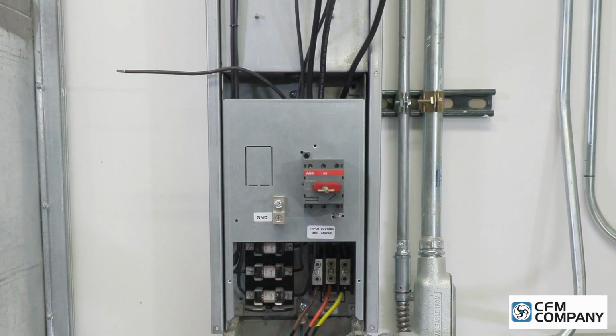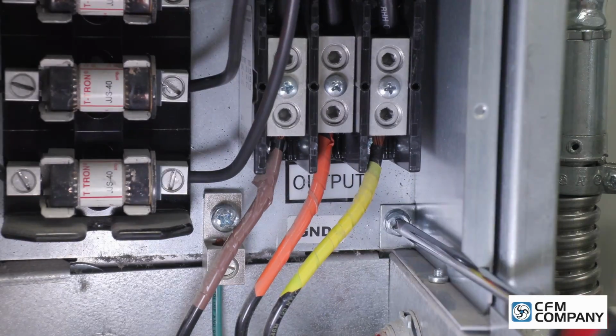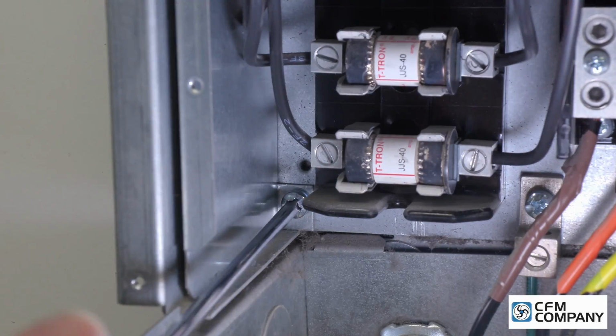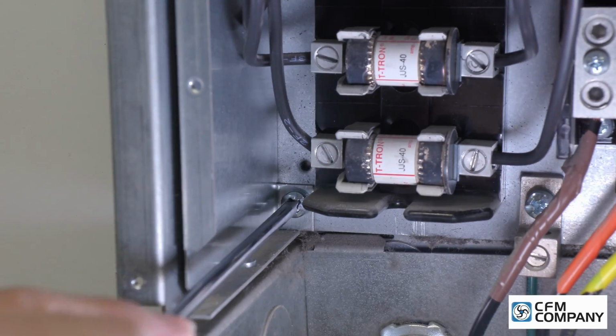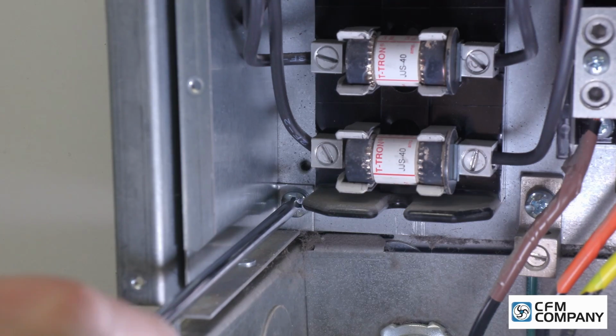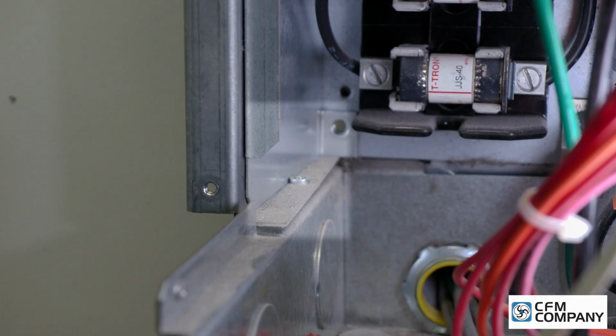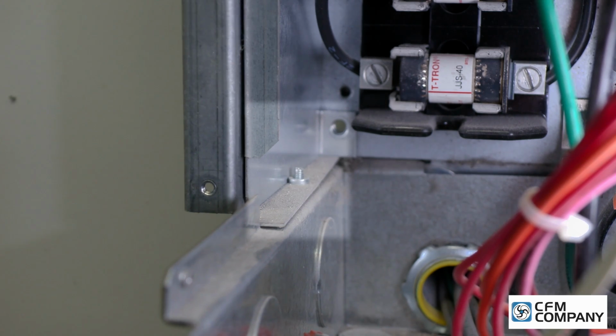Next, the front disconnect plate is installed with the 3 power wires pulled over the top. Secure the front disconnect plate with the 2 number 3 Phillips screws. Install the screw into the lower right bracket next to the motor terminal block. Install the second number 3 Phillips screw on the lower left bracket next to the fuse block. Not shown: if the screws holding the lower conduit box were loosened to remove the front disconnect plate, tighten them to secure the conduit box.